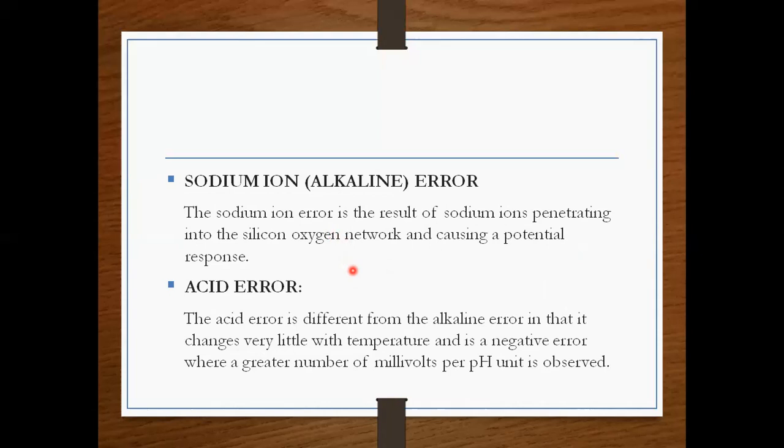As the hydrogen ion activity becomes very small, these ions can compete successfully in the potential determining mechanism. Although the hydrated gel layer prefers protons, sodium ions will exchange with the protons in the layer when the hydrogen ion activity in the external solution is very low. So when the hydrogen concentration is low, the sodium ions replace their position in the hydrated gel layer and cause the potential to increase or decrease. This is what occurs in the sodium ion error.